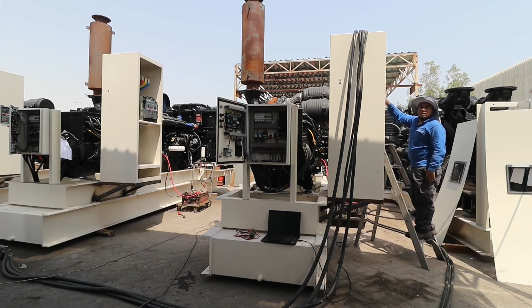So as you can see, I'm coming back and going to the breaker side. I'm going to tighten the breaker in order to close properly our breaker, because it was not tightened by the guys who did the installation for this. They maybe forgot to tighten it, because this breaker is different from the other breaker. You can roll out this breaker and you can roll in also. So it is a removable breaker, as you can see. Now I think it's done.